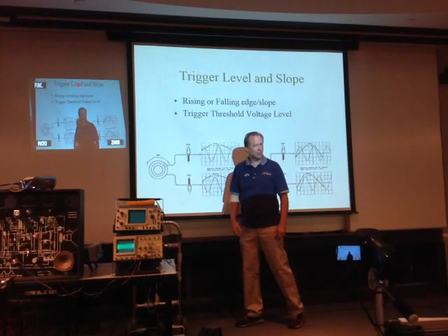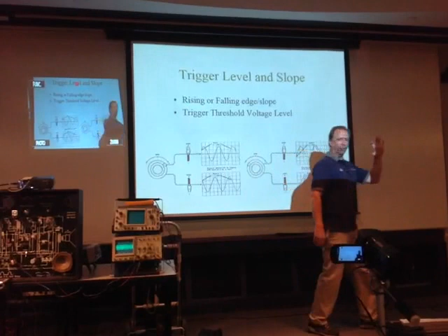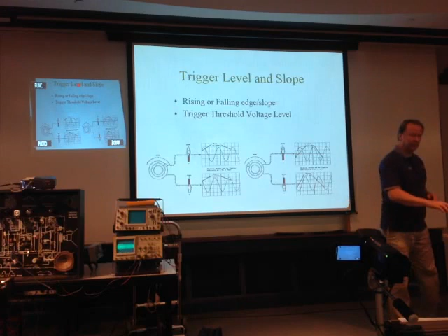And again, what you can do is flip the switch up to positive, and set your level control right to the middle. You have your AC coupling, so you can be right in the middle of your waveform. And you should get a triggered sweep without a problem. Okay? With line triggering, you don't have to worry about those. It just automatically triggers on the line. It doesn't really matter what you set those to. You can change the slope, but the level control really won't matter. Okay? Make sense?